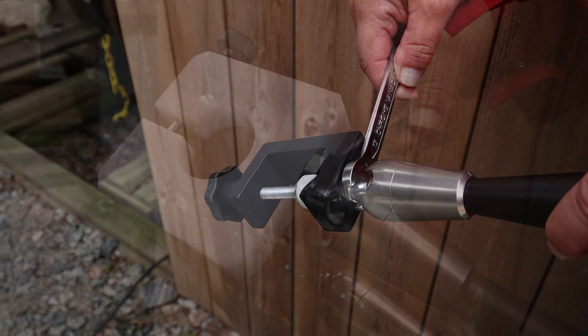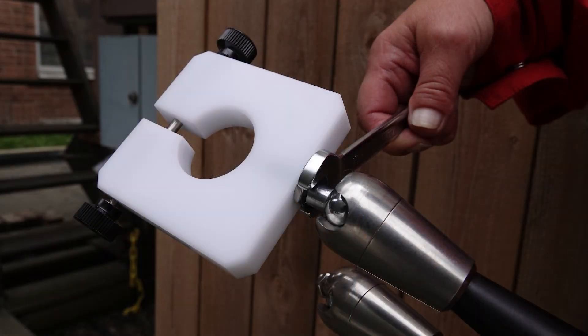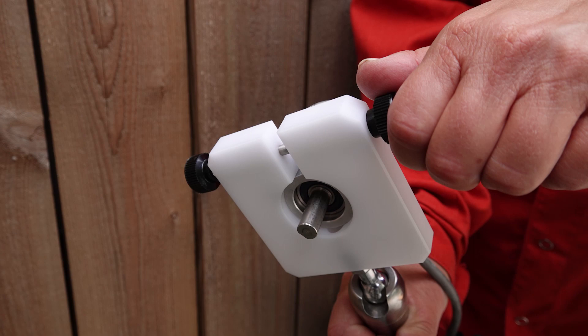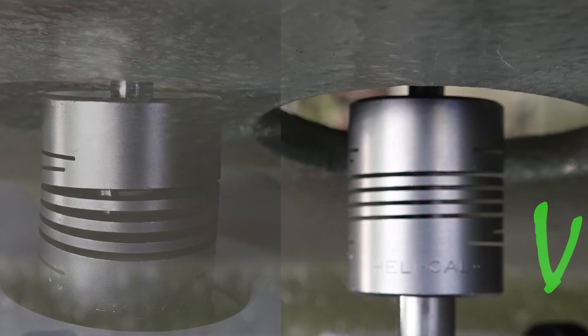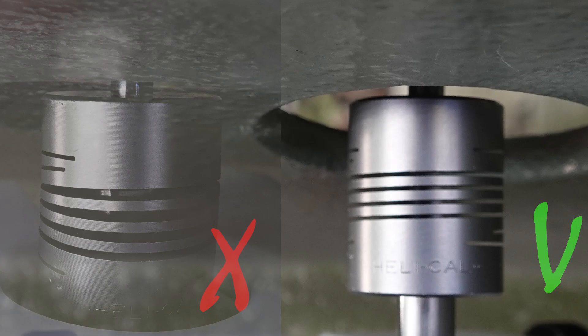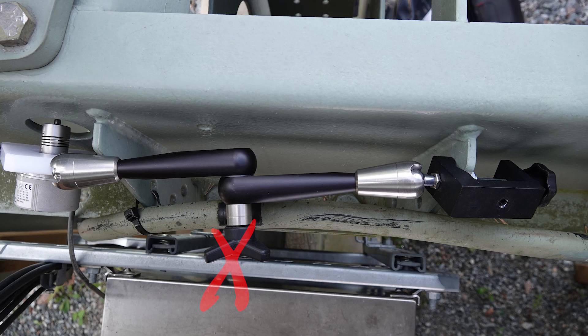Make sure you mount the parts with space between each component. The flex coupler must not be stretched or pressed, but needs to move freely to cover any misalignment. The whole setup must be mounted in a straight, strong, and steady position.